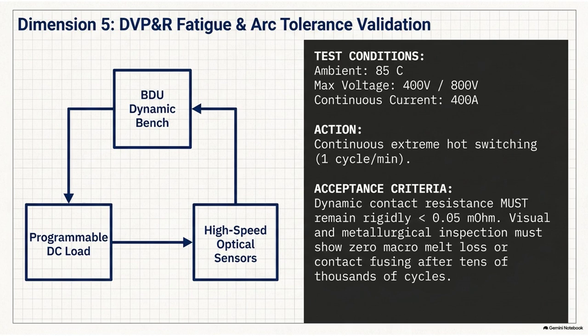400 amps of continuous current. That is an enormous, terrifying amount of raw energy flowing through that relatively small switch. And then, while that immense current is flowing at absolute maximum capacity, the computers intentionally command the relay to hot switch. They force the contacts to rip open under the full 400 amp load. They intentionally create the devastating DC plasma arc, the thousands of degrees of localized heat, right there inside the 85-degree oven. They rely entirely on the internal nitrogen chamber and the passive magnetic blowouts to extinguish the lightning bolt before it destroys the rig.